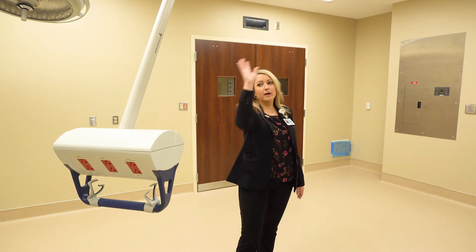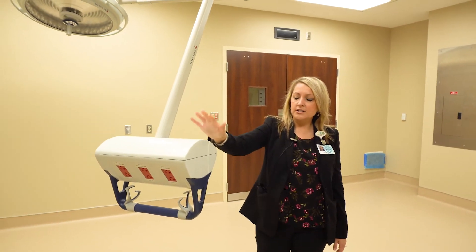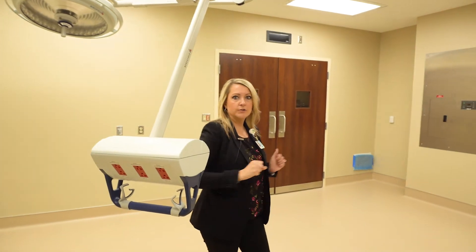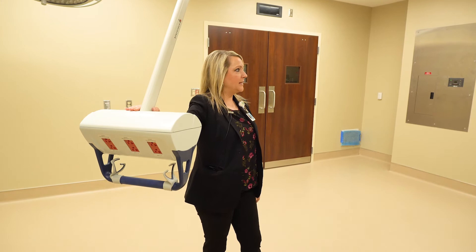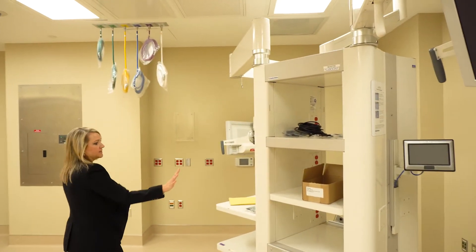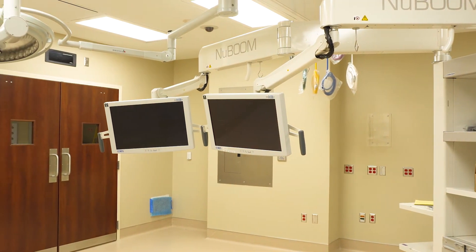In here, we have the same sort of setup with surgical lights. We have our VPAs, which are additional power, voice, and data for any sort of equipment that we may need to get power closer to the area rather than having cords draped across the floors. We have our VPA arms. The NuBoom monitors — this is the NuBoom. This was set up originally in our cysto suite and will allow the surgeon to bring these monitors right to the top of the patient bed. We designed it such that we have dedicated space for the laser, which they'll use occasionally depending upon the procedures in this space.